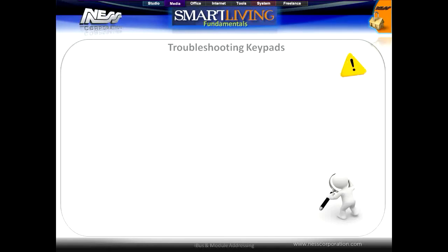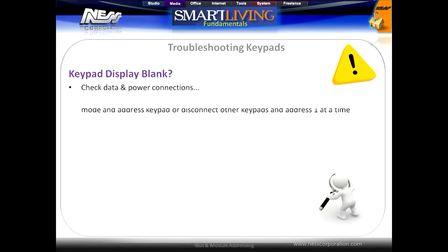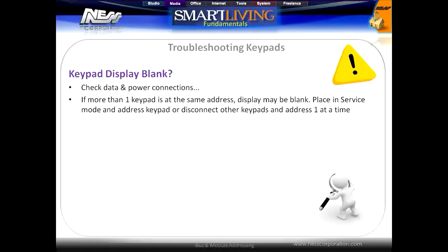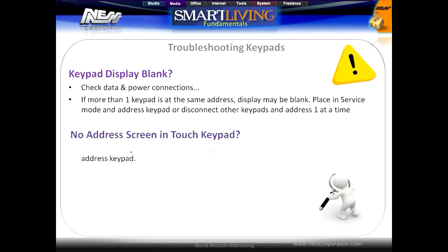Some basic troubleshooting for keypads: if the display is blank, first check the power and data connections. If there is more than one keypad on the system and the display is blank, it probably means that more than one keypad is set to the same address. Place the system into service mode and go to each keypad to set the address. If the address setting is not listed in the touchscreen, it means that the system is not in service mode.